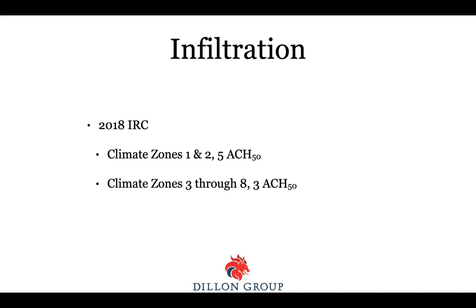I did a bunch of work for a builder one time where we just averaged their blower door test results for this plan. And we said, plug this into your load calculation. Here's the average test results. We know the code requires, it's written in the code book. Plug that in as the worst house they can legally get away with for infiltration.